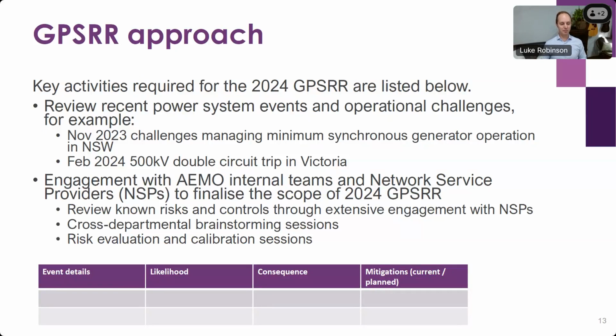Really, the starting point in our development of each risk review is to look at what's happened on the power system. What have we actually seen? Where have we seen operational challenges in how we manage the system? And where have we seen major events where there have been learnings from those events? A couple of recent examples just to highlight would be in November of last year, we saw challenges in managing the minimum synchronous generator operation in New South Wales. And that demonstrated the potential for those challenges to evolve over time as we move to fewer synchronous generators online in New South Wales, and flagged to us some of the challenges we'd need to manage.